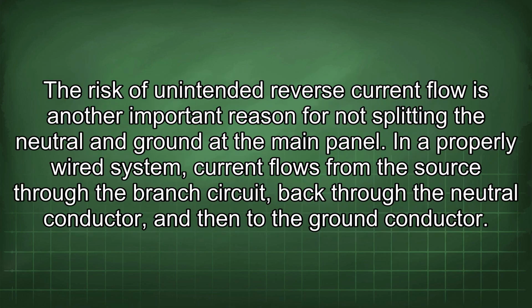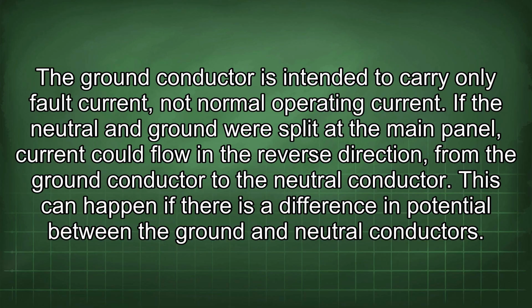The risk of unintended reverse current flow is another important reason for not splitting the neutral and ground at the main panel. In a properly wired system, current flows from the source through the branch circuit back through the neutral conductor, and then to the ground conductor. The ground conductor is intended to carry only fault current, not normal operating current. If the neutral and ground were split at the main panel, current could flow in the reverse direction, from the ground conductor to the neutral conductor. This can happen if there is a difference in potential between the ground and neutral conductors.